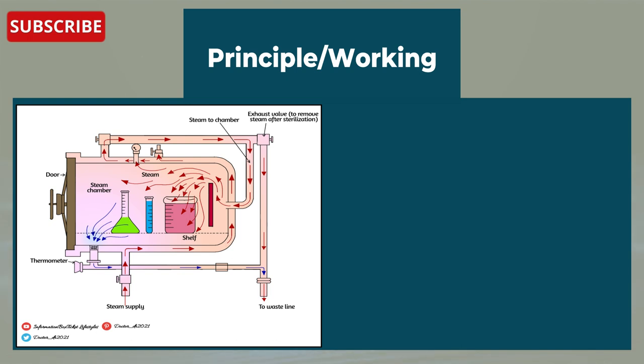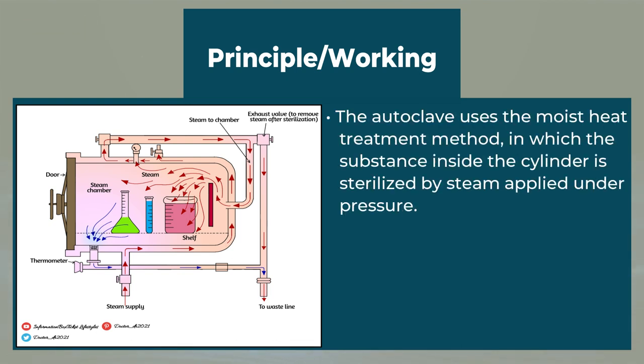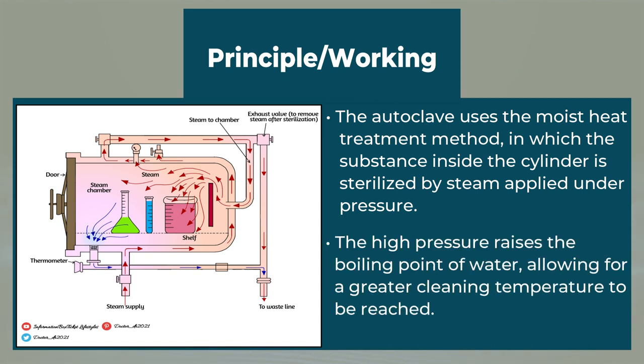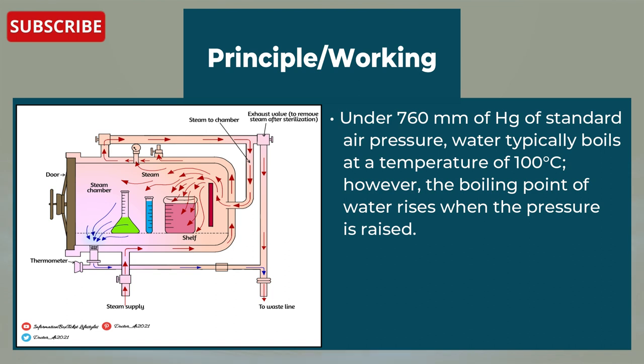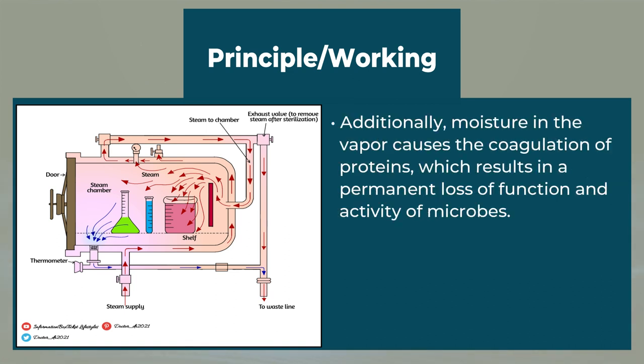Now let's dive into the autoclave principle or working. The autoclave uses the moist heat treatment method in which the substances inside the cylinder are sterilized by steam applied under pressure. The high pressure raises the boiling point of water, allowing for a greater cleaning temperature to be reached. Under 760 mmHg of standard air pressure, water typically boils at 100 degrees Celsius. However, the boiling point of water rises when the pressure is raised. Additionally, moisture in the vapor causes the coagulation of proteins, which results in a permanent loss of function and activity of microbes.